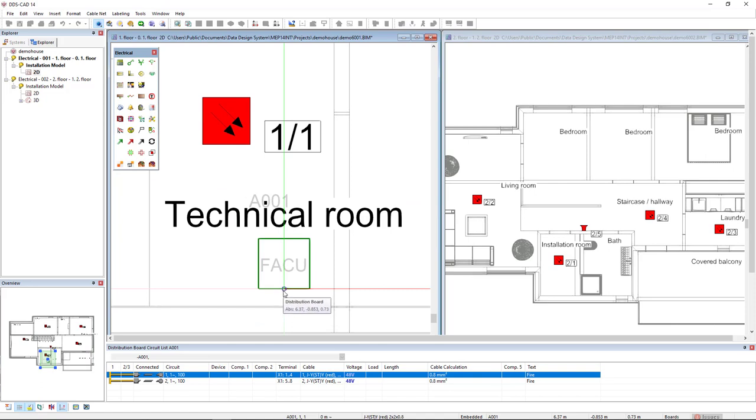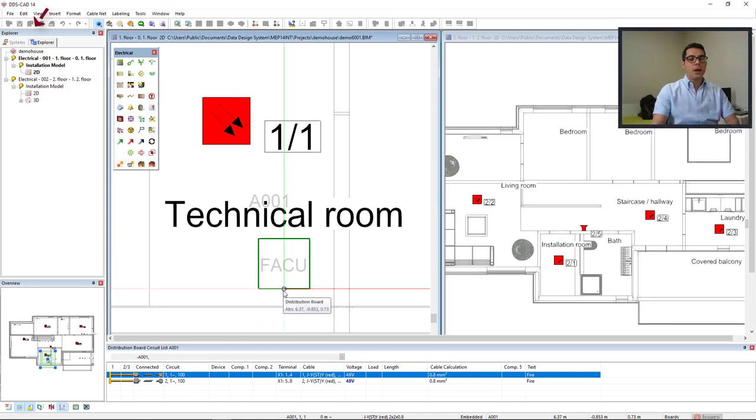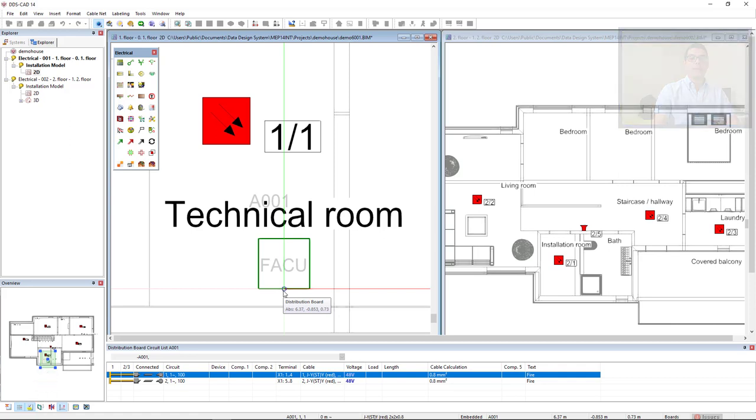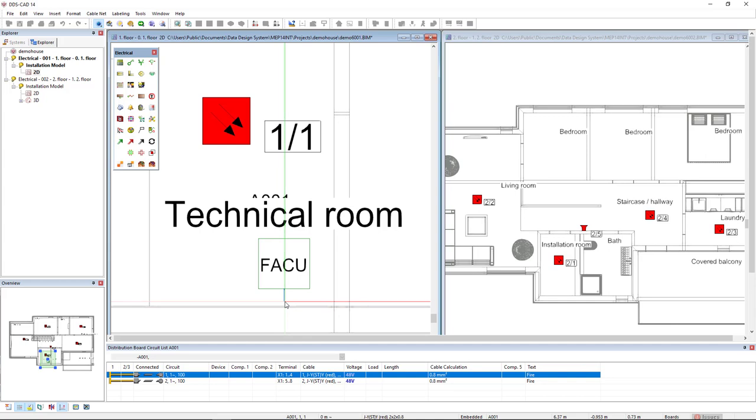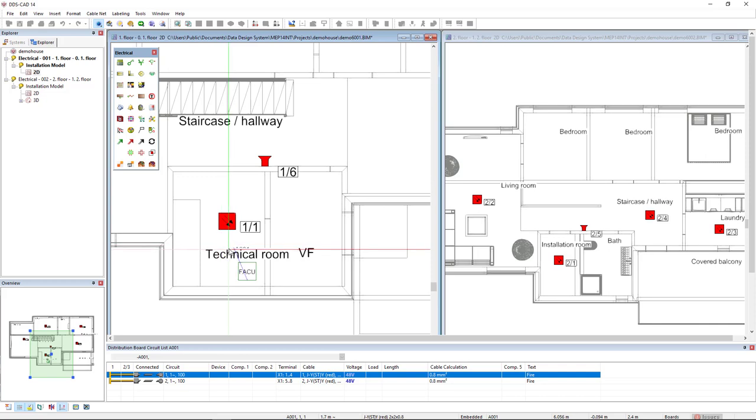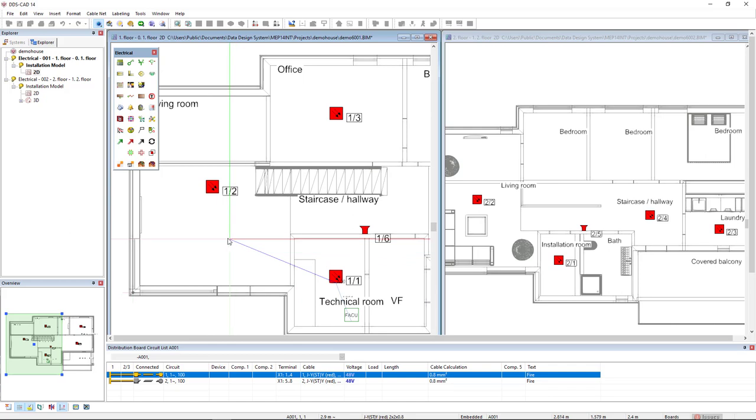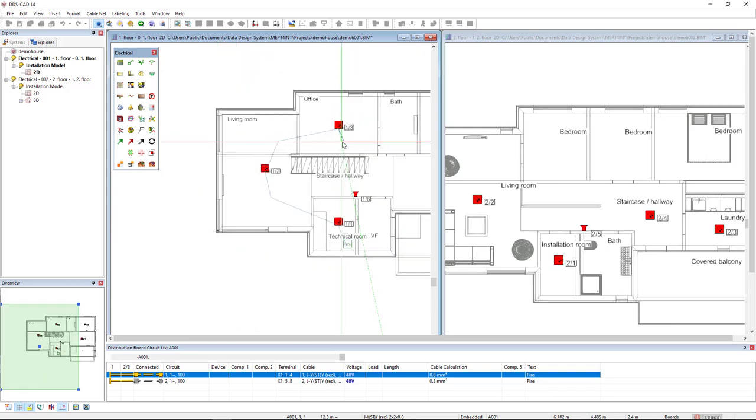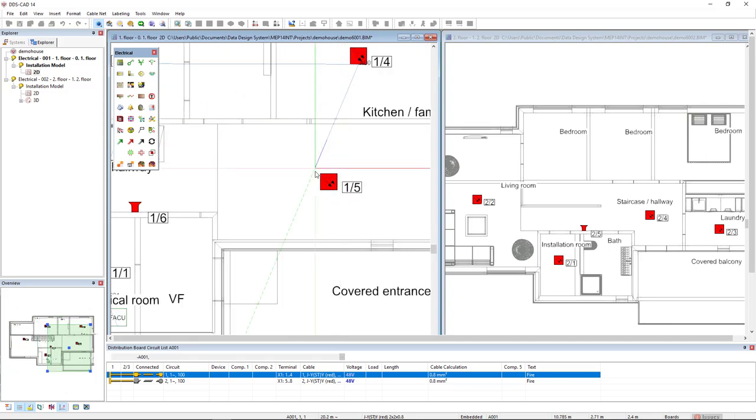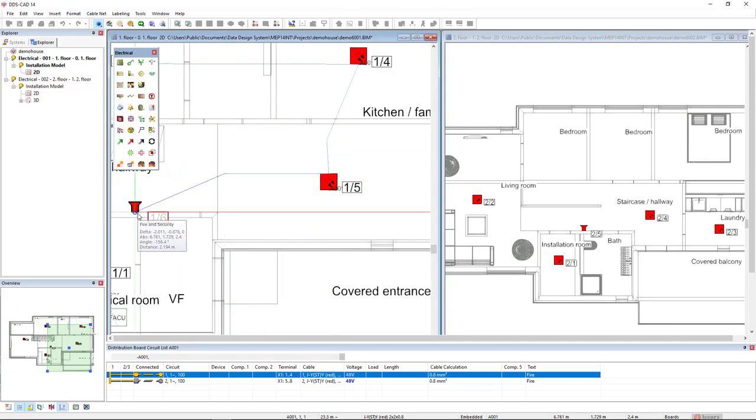I click OK and I will move close to the board and as you can see a connection is recognized. And bear in mind, remember that the function use smart snaps must be activated in order to highlight the connections. I'll click here and I will change the mounting height by using a hotkey called page up in my keyboard. In absolute z plus I inserted a new mounting height which will be 2.4 meters. Click OK and now I will click and move and connect to the objects following the sequence of the position marker.